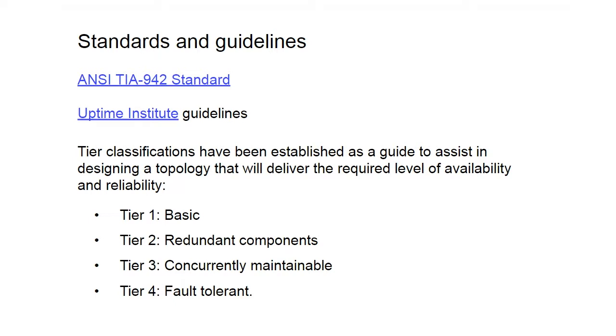A tier one is a basic system, maybe a generator, UPS, not a lot of redundancy, not a lot of bypass. Tier two is where you start implementing redundant components, maybe an N plus one generator, N plus one UPS. A tier three is basically set up with a lot of bypass systems, so you could put a system in bypass while you maintain that system. It's live. You don't have to shut the system down. And then tier four is more fault tolerant. That's where you start to see fully redundant systems, a 2N system, where if you have a fault, the system swings to another system and it still maintains its availability and reliability during the failure.